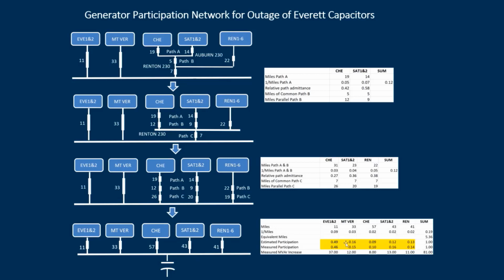This is the estimated participation of the megavar flows in each of those paths for the loss of this shunt capacitor. If we actually take the measured megavar increase of those generators, when we remove that shunt capacitor, that's the numbers that we have down here. And the measured participation is the proportion. In that case, each of these generators responded for a total of 81 megavars. And if we take the proportion, this is the measured participation, and we can see that this measured participation agrees quite closely with the estimated participation as shown here.